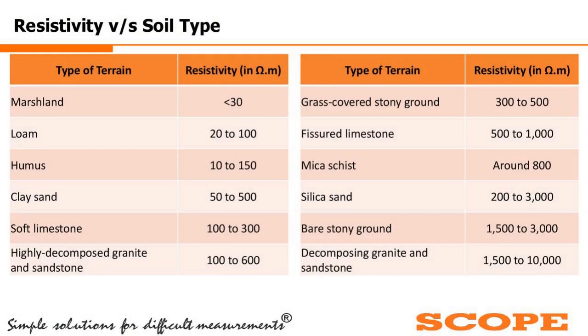Now let us have a quick look at the different types of soils and their resistivity. This is just a rule of thumb, which is available in the IEEE standard. We have just mentioned this as a reference. The different types of soil, like marshland, will be getting less than 30 ohm meter. A loam kind of surface will be getting 20 to 100. Humus soil will be getting 10 to 150. Clay sand will be getting 50 to 500. In that fashion, it is going.